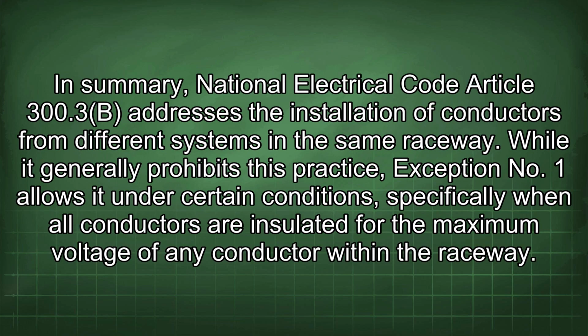In summary, National Electrical Code Article 300.3(B) addresses the installation of conductors from different systems in the same raceway. While it generally prohibits this practice, Exception No. 1 allows it under certain conditions, specifically when all conductors are insulated for the maximum voltage of any conductor within the raceway.